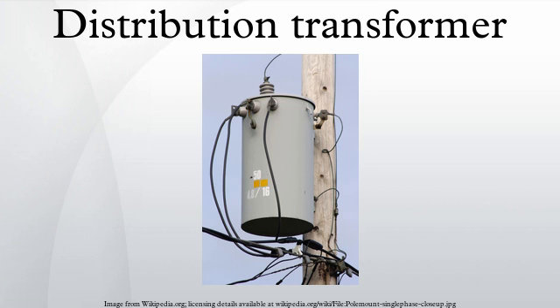Distribution transformers are made using a core made from laminations of sheet steel stacked and either glued together with resin or banded together with steel straps. Where large numbers of transformers are made to standard designs, a wound C-shaped core is economic to manufacture. A steel strip is wrapped around a former, pressed into shape, and then cut into two C-shaped halves which are reassembled on the copper windings. The primary coils are wound from enamel-coated copper or aluminum wire, and the high-current low-voltage secondaries are wound using a thick ribbon of aluminum or copper. The windings are insulated with resin-impregnated paper. The entire assembly is baked to cure the resin and then submerged in a powder-coated steel tank filled with transformer oil, which is inert and non-conductive. The transformer oil cools and insulates the windings and protects the transformer winding from moisture, which will float on the surface of the oil.